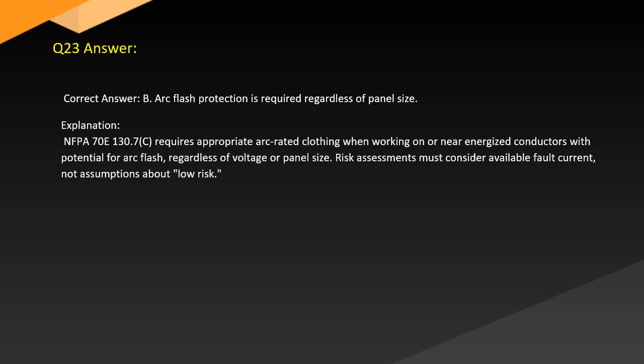Answer. Correct answer: B. Arc flash protection is required regardless of panel size. Explanation. NFPA 70E 130.7(C) requires appropriate arc-rated clothing when working on or near energized conductors with potential for arc flash, regardless of voltage or panel size. Risk assessments must consider available fault current, not assumptions about low risk.